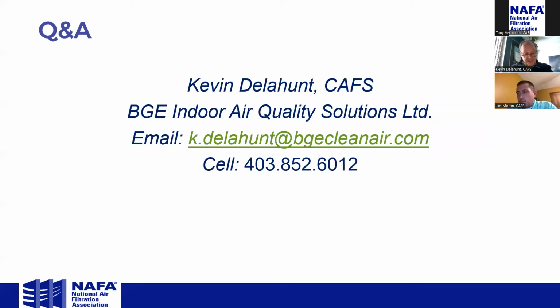UVC is an excellent add-on product to filtration, and they work synergistically on different contaminants: filters on particulate, UVC on biological contaminants. As well, UVC works great on evaporative cooling coils for airborne virus and bacteria when sized correctly. So it's not going to change the overall MERV number, but it is going to provide you an increased system efficacy, I guess, would be the best way to put it. Each one doing its own job.